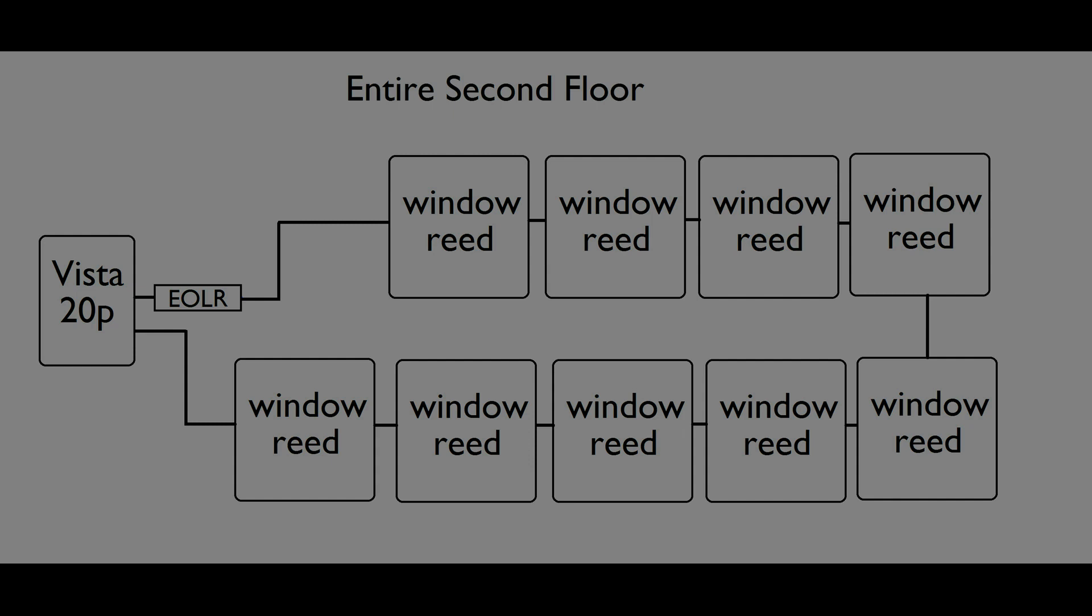You could use one loop to protect every single window on your second floor. And it would work, as long as the total loop resistance outside of the end of loop resistor doesn't exceed 300 ohms. Granted, this is a bad design, but it's much better than having no protection at all.